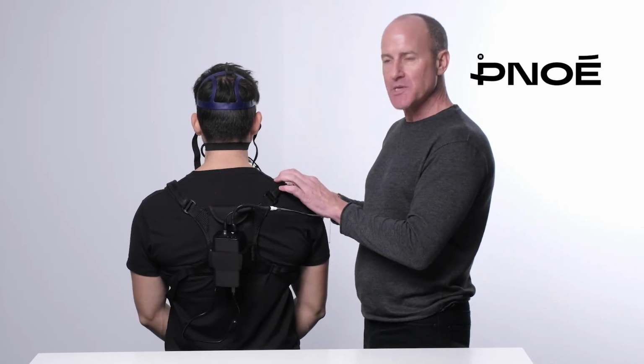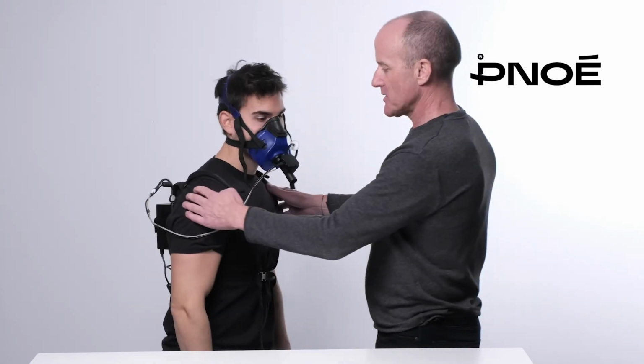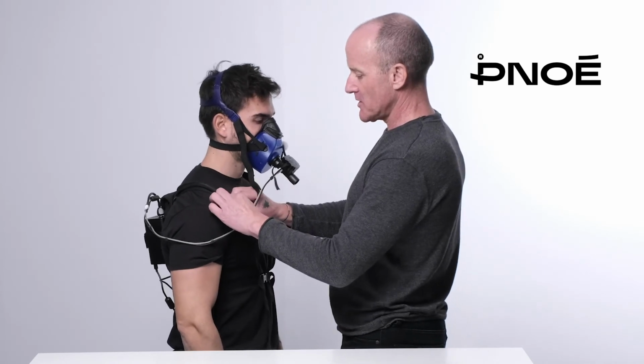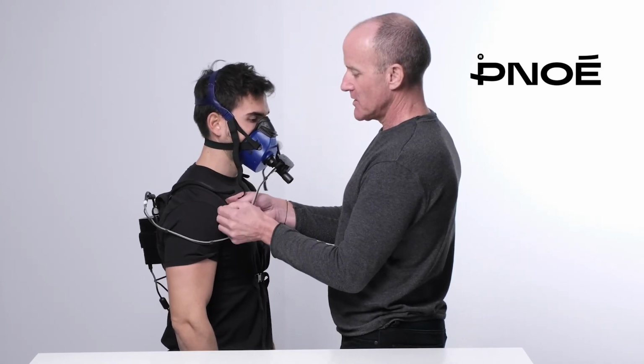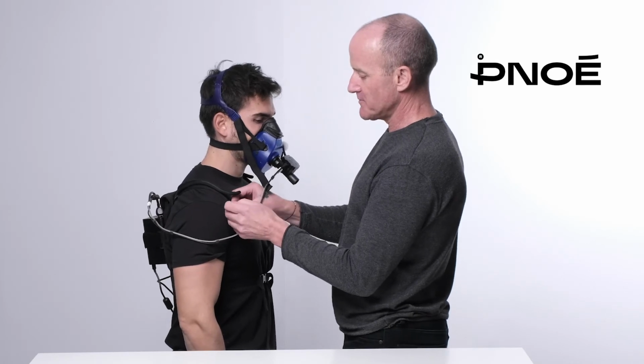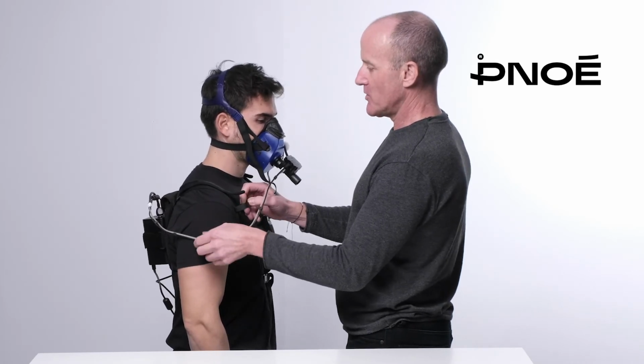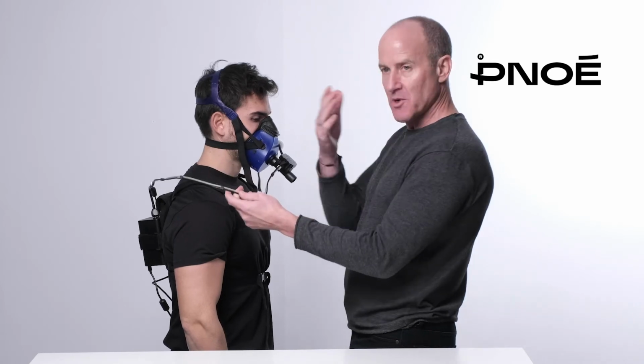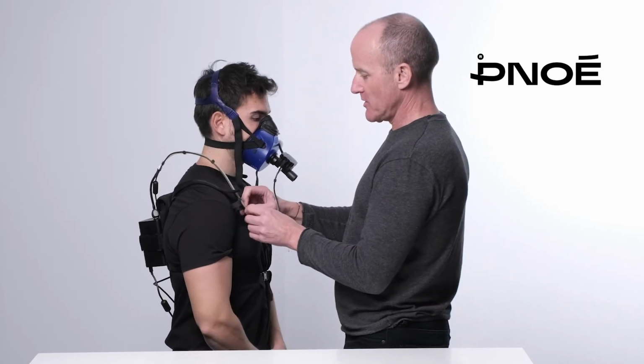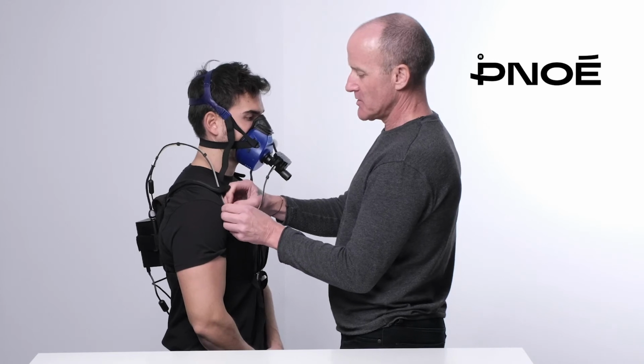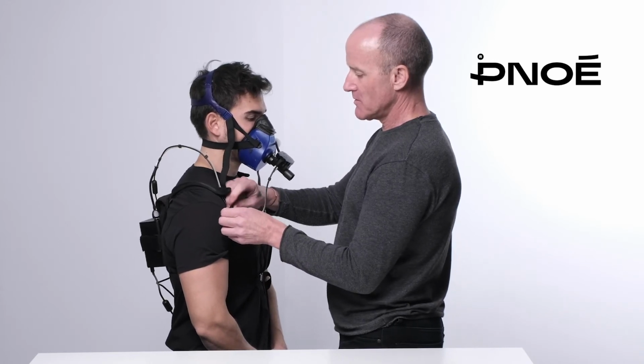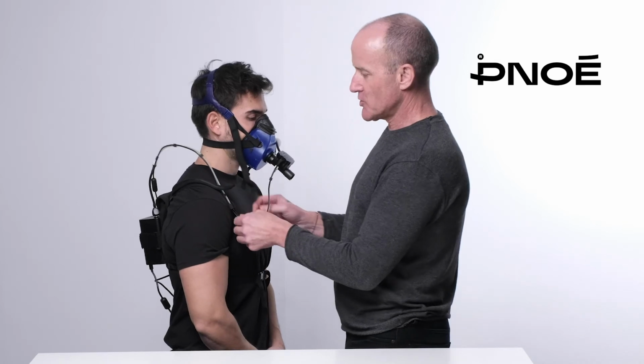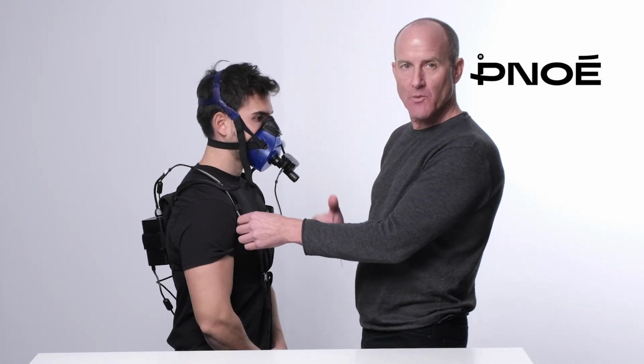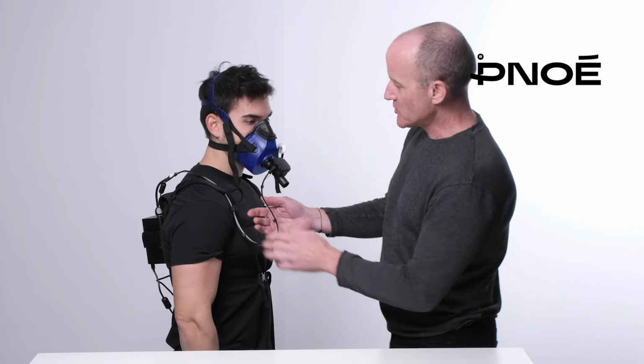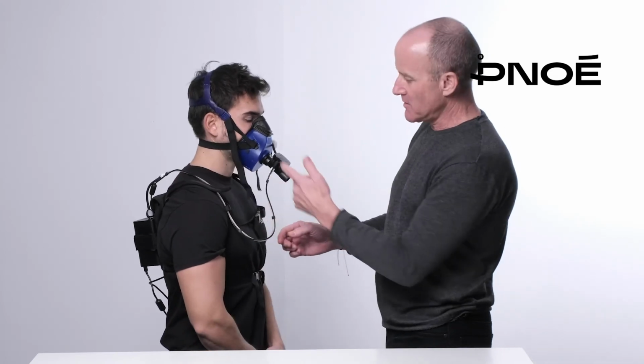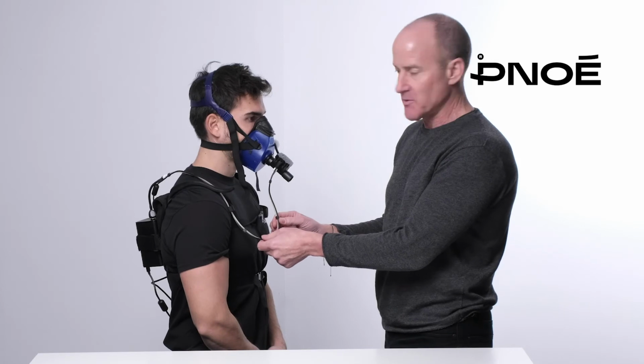The last thing you do, after you get everything fixed in place, is you'll notice that there's a small ring here that opens up. And you can feed your cabling, which should always be over the right side of your customer, in position to ensure that the cabling itself does not get in the way of the arm movement. Make sure that there is no tension on the power cable and the flow sensor cable itself.